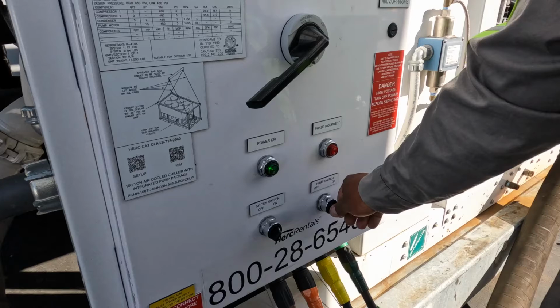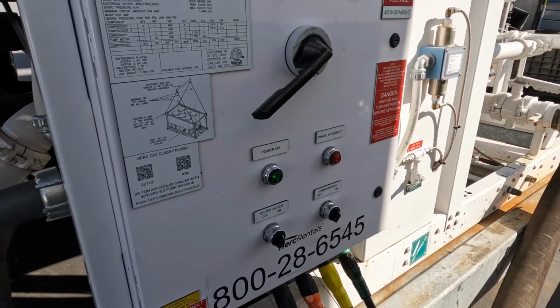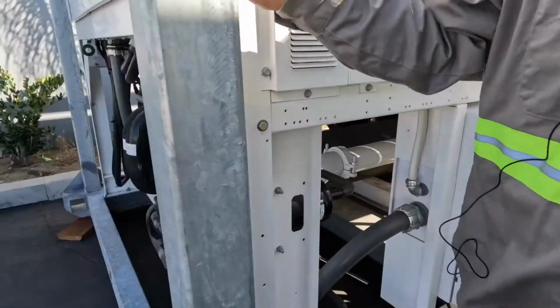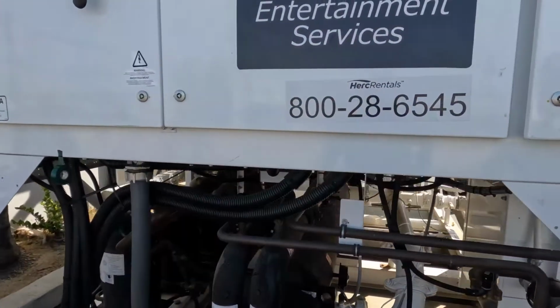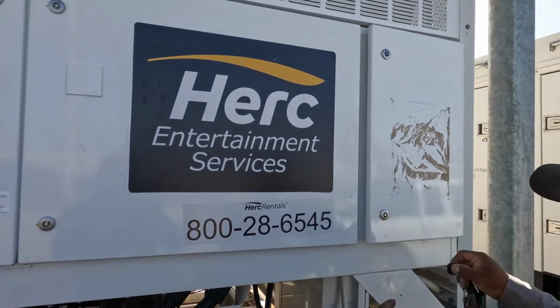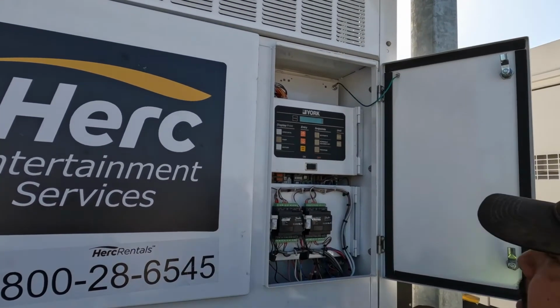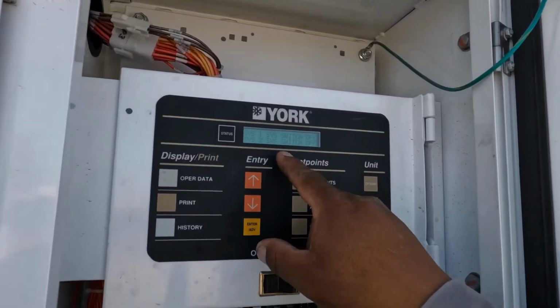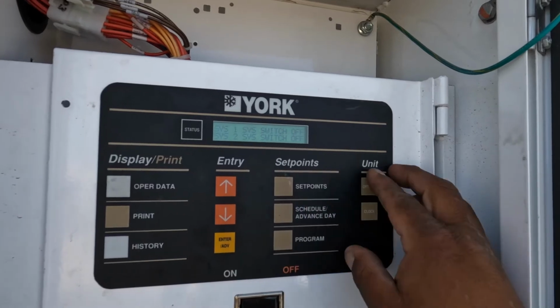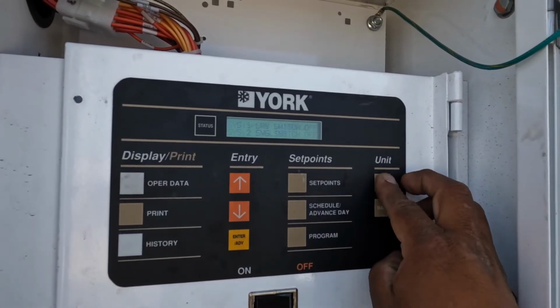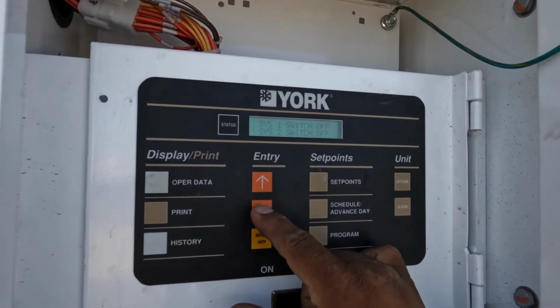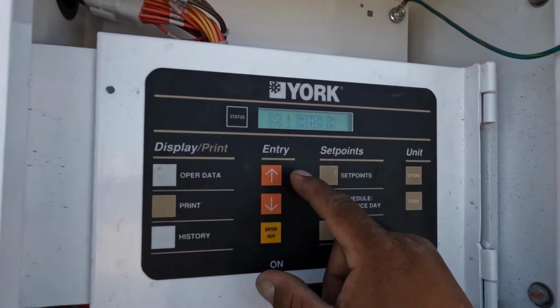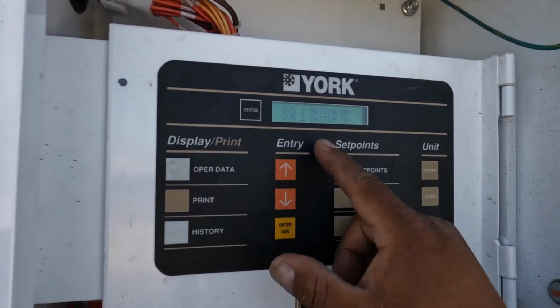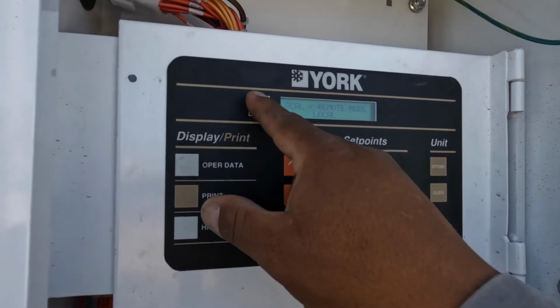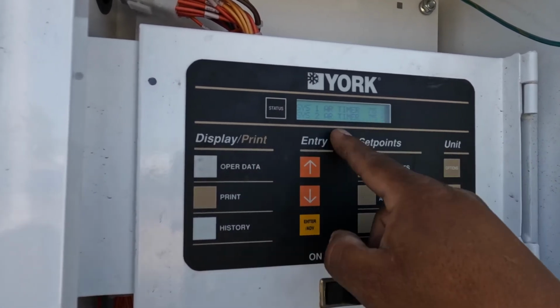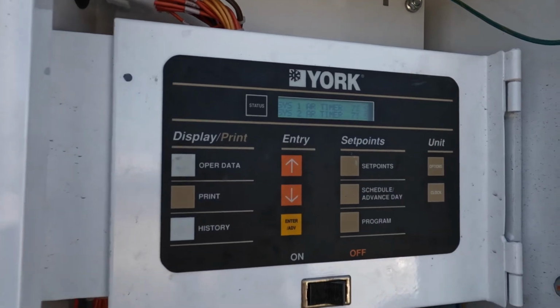You go to system switch, hit the pump, you'll hear the pump running. Then you come back here to the side. Then you come here and you see it says system switch off. Then you go to options, 1, 2. You go arrow up, system 1 switch on, system 2 switch on. You press enter. Go to status, and you'll see the timer running down. Once the timer gets to 0, you'll hear the compressor.